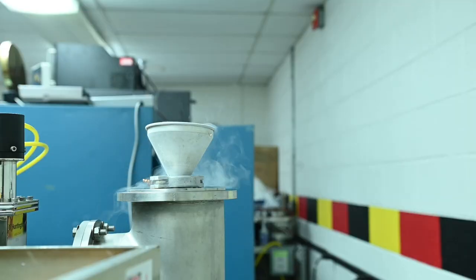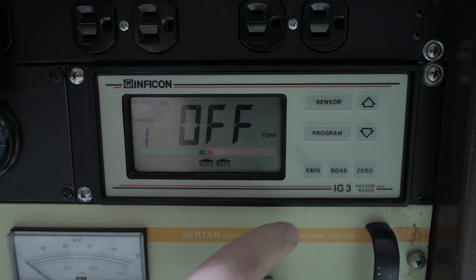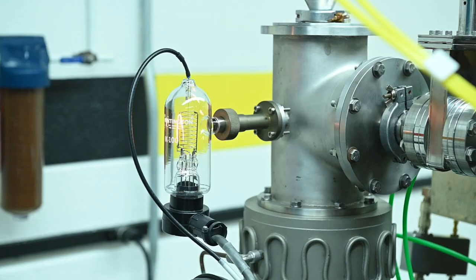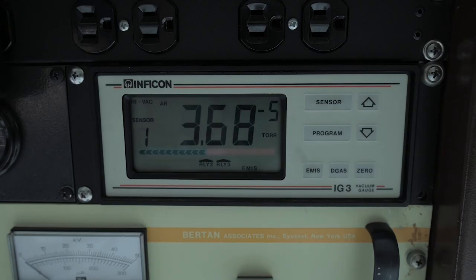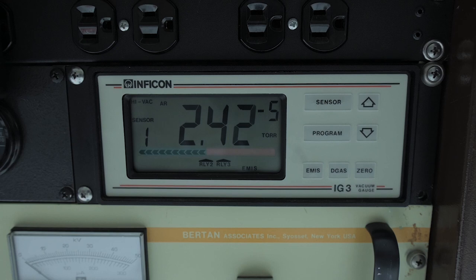The pressure at this point will begin to drop and go below the range of the Pirani gauge, so we switch from the Pirani gauge to the ionization gauge readout. As the diffusion pump heats up, it begins to efficiently pump, and the pressure drops from the millitorr range down to the microtorr range. Once the pressure is in the microtorr range, there is sufficiently little air in the chamber such that the cyclotron beam may be turned on.